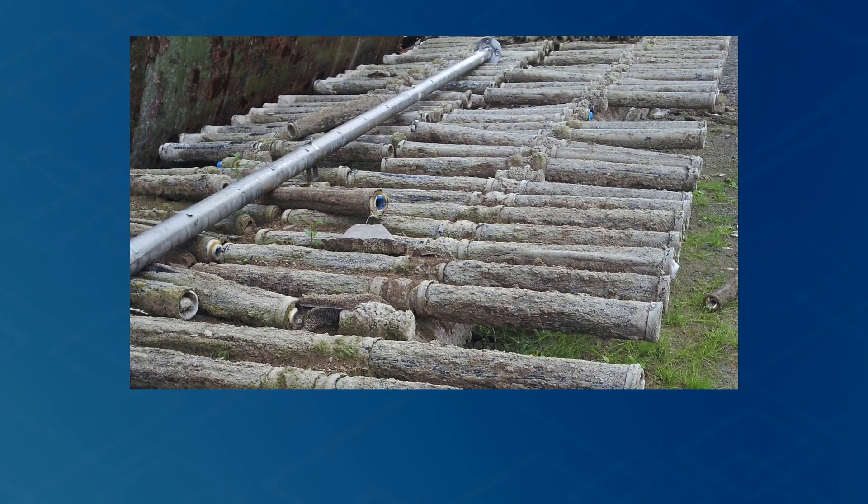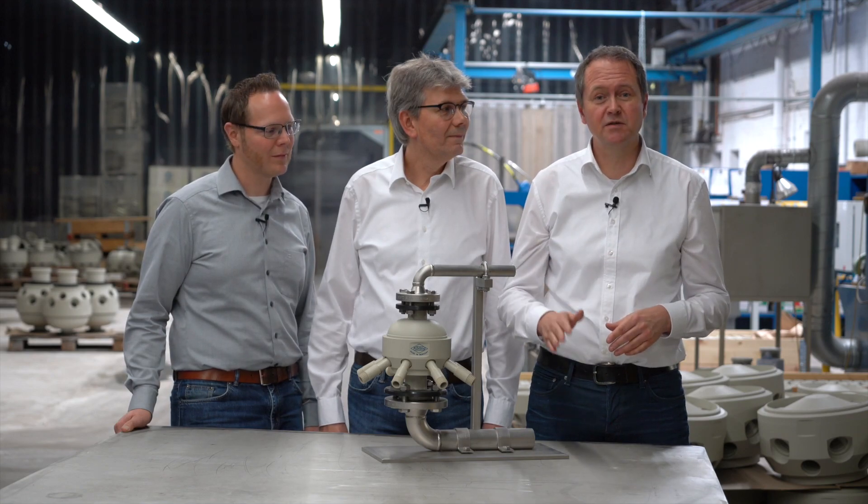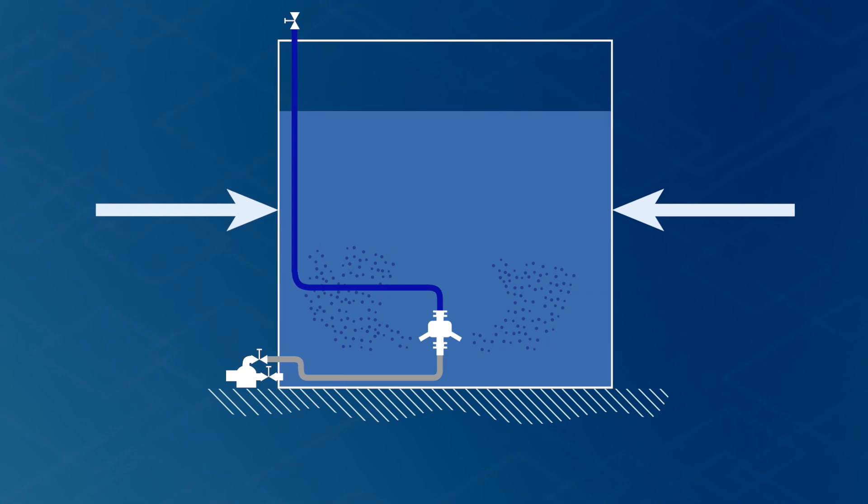In contrast to membrane aerators, ejectors don't cause any scaling or fouling. Safety margins are not required when designing ejectors. The alpha factor for ejectors is a lot higher than in other oxygen transfer systems. In contrast to conventional aeration systems, ejectors can also be used in very deep water, which cuts the footprint of the tank dramatically.